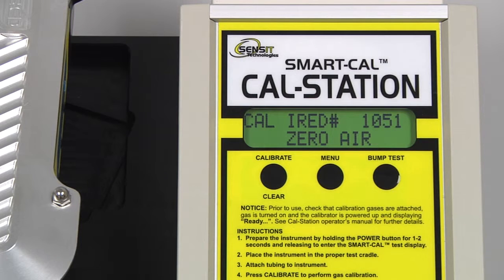The first portion of the calibration is zero air. After the instrument achieves a stable reading, the internal cell will actuate into the light path. And the instrument again will wait for a stable reading. After a stable reading is achieved, the instrument will either perform a re-zero or advance to the next portion of the calibration. In this case, no re-zero was required, and the instrument is now calibrating 100 parts per million ethane.